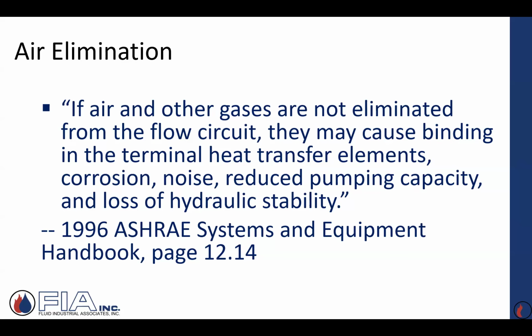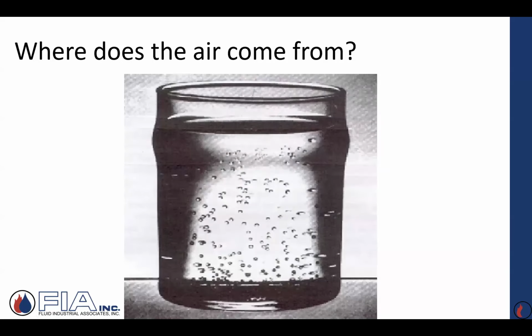You're unloading or deloading an impeller that's spinning at a certain RPM with a certain load, and all of a sudden a volume of air comes in. It's going to reduce pump capacity as well as hydraulic stability. We'll explain that a little bit later on, but I don't want air floating throughout the system. It can wreak havoc with the operation of the pump as well as all these other elements, these maladies that can take place. So where does the air come from?